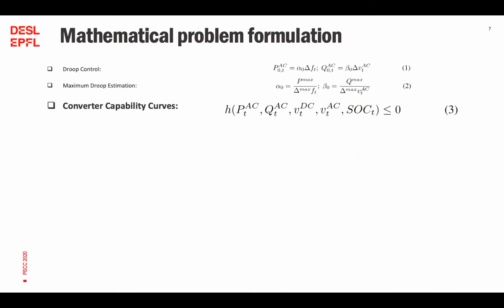The formulation, of course, considers the selection of the capability curve as a function, as I said, of the AC grid voltage and the battery conditions, such as state of charge and DC bus voltage. So we extracted the piecewise interpolated lines for each curve, and we could obtain the coefficients for the different DC voltage and AC voltage conditions. And these curves are used as constraints in the computation of the PQ set points. Note that H is a complex constraint since it is built from a circular constraint on the apparent power and 2 box constraints on the active powers.